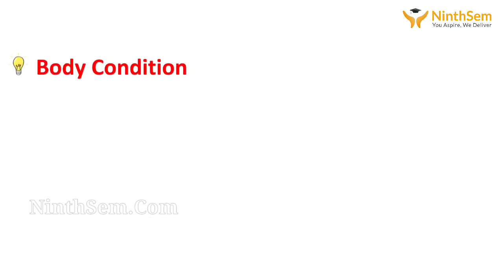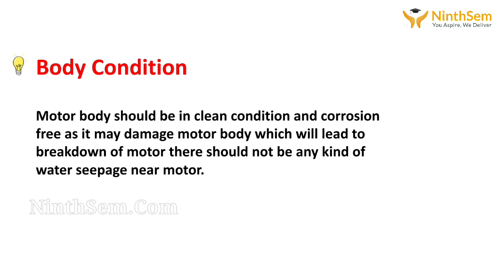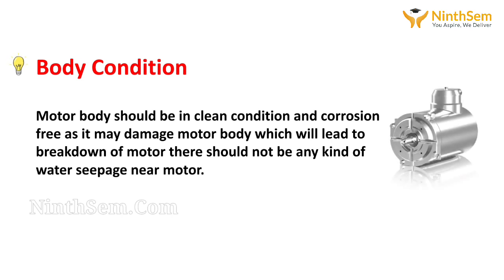Body condition. Motor body should be in clean condition and corrosion free, as it may damage motor body, which will lead to major breakdown of motor. There should not be any kind of water seepage near motor.